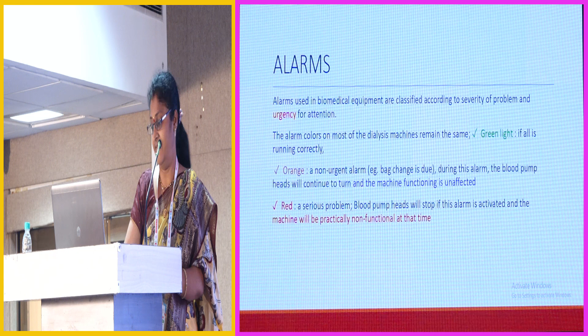So we all know this. Alarms used in biomedical equipment are of 3 categories: green, orange and red. What I would like to understand is that when a patient is on CRRT, we don't want any downtime, because since morning all the speakers have been telling you that the delivered dose is different from the prescribed dose, and there are various reasons for this. One important reason is that there should not be many alarms or breakdowns in the circuit. When you see a red alarm in CRRT, that is very important, because the machine will be practically non-functional. In intermittent hemodialysis that doesn't make a big difference, but in CRRT it makes a big difference because it affects the dose delivered.